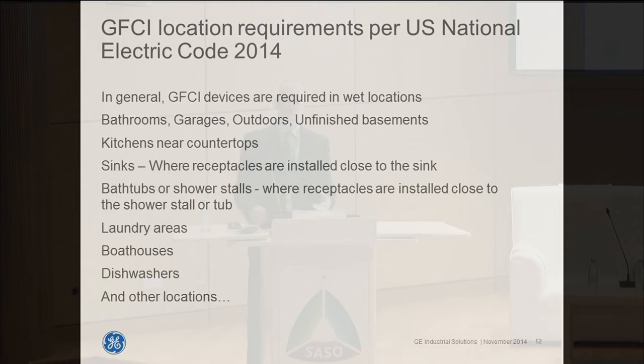At this point in time, the code is very comprehensive, really with the mindset of identifying any place where a human can come into contact with a wet location. And probably some other areas not mentioned here, any receptacles feeding outdoor areas where you might have random contact with wet areas, those are also important. So in this environment it's mostly dry outside, except for last night, but clearly inside it's important to have these devices required.